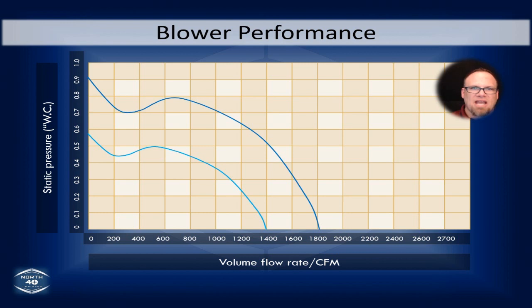But at 1 inch of static, if you were to put a dot right on that line, clear over by 1 inch of static, how much CFM do you have? You have 0. So at the most amount of resistance, you have the least amount of airflow. Now look at it from the other direction. Go down to the bottom horizontal chart. You see those numbers across the bottom, which is CFM. That's how much air is actually moving while that fan is running.